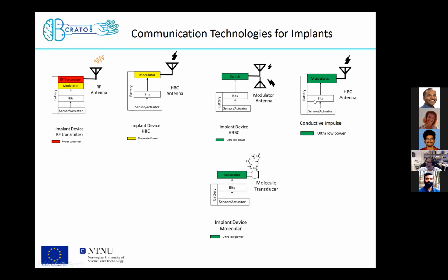The other way is by using conductive impulse, for which we have shown the feasibility for implant-to-implant communication. This is similar to human body communication where a low frequency signal is used, but here we use an impulse signal, which is like a baseband impulse from very low frequency, several hertz, up to maybe 1 megahertz or less. In this way, we limit the transmitted power to a single pulse. And also the electronics used in this system are quite light. And in this way, we can convey low data rate information, on the order of hundreds of bits, but at very low power, on the order of tens of picowatts per bit.